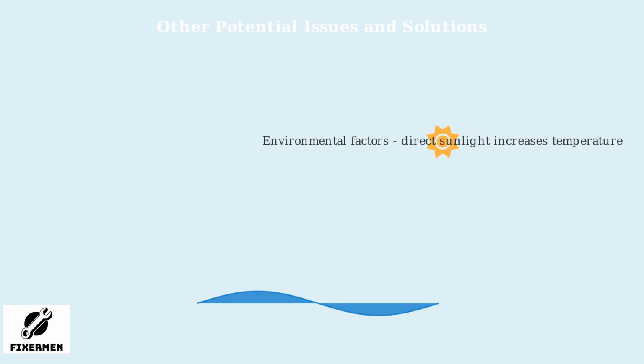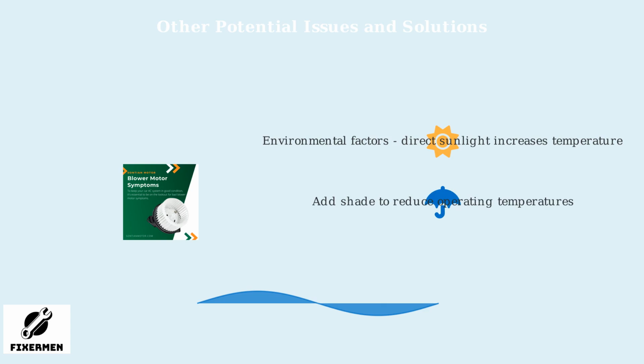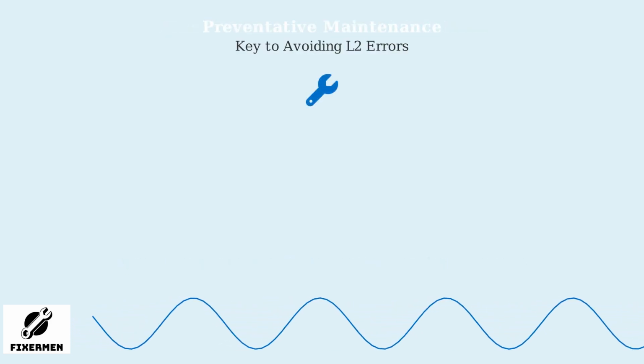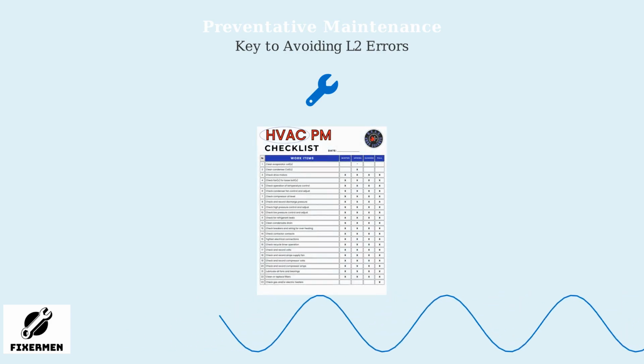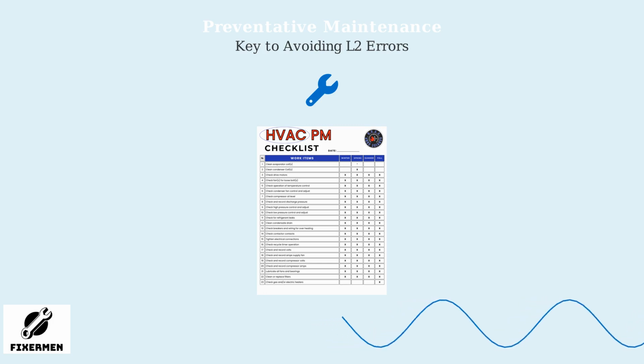Environmental factors like direct sunlight exposure can exacerbate the problem by heating the outdoor unit excessively. Adding shade, such as an awning or vegetation, can help reduce the unit's operating temperatures and prevent L2 errors. These components and environmental factors should always be inspected and addressed by a qualified HVAC technician to ensure safe and proper repairs. Regular preventative maintenance is essential to prevent Lennox AC error code L2.